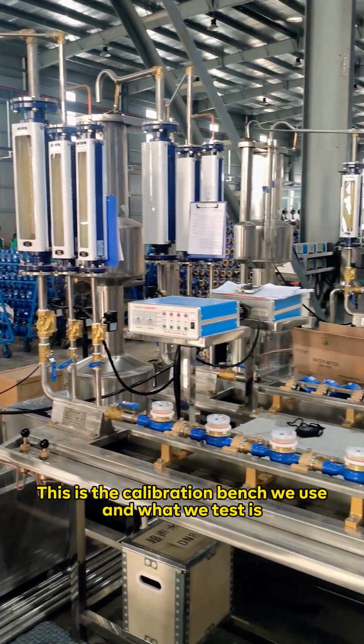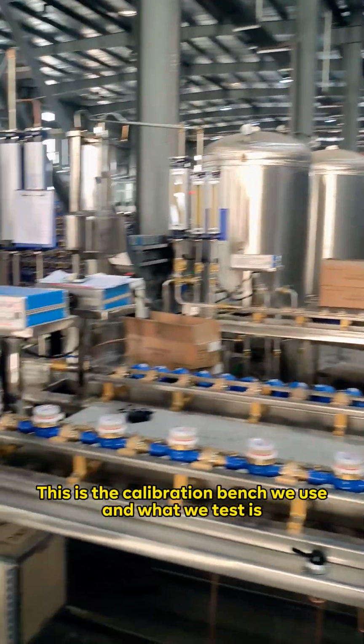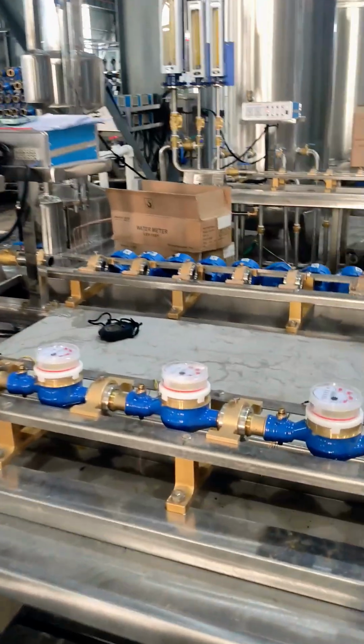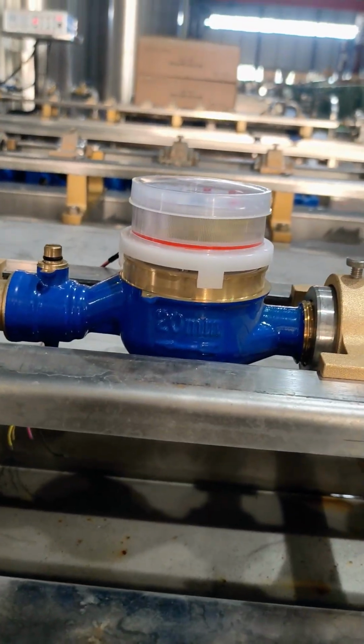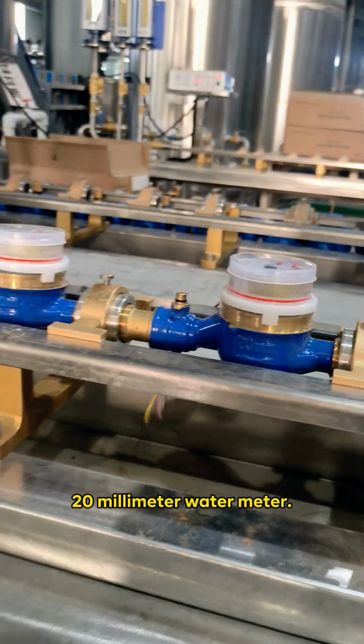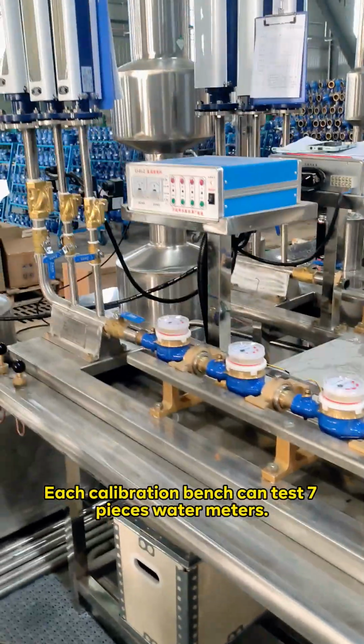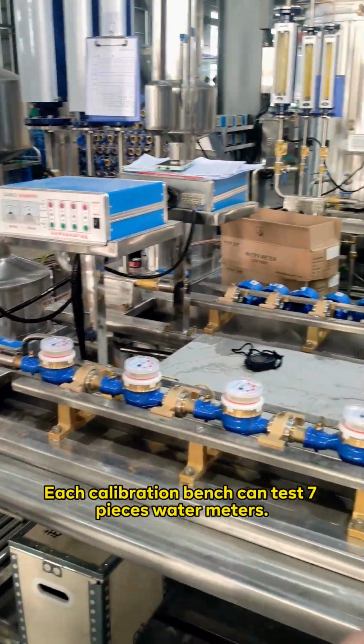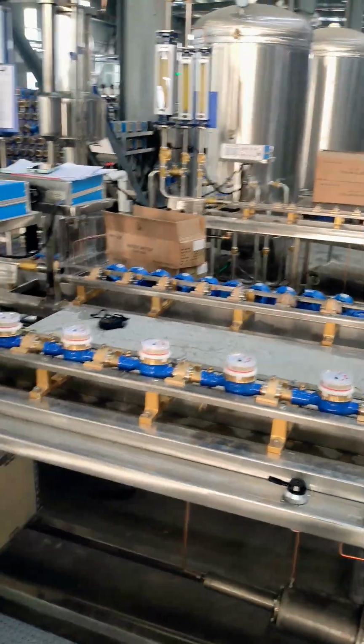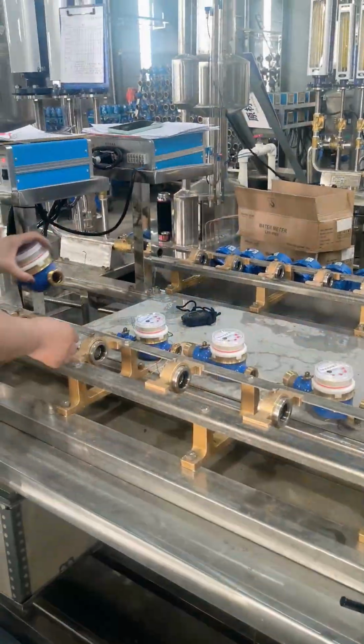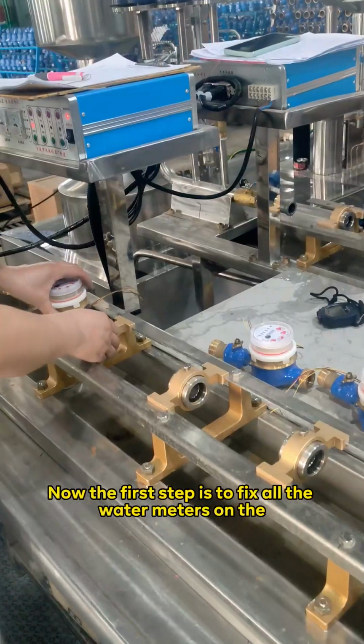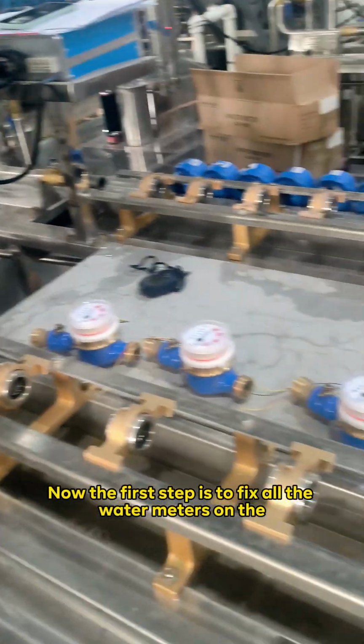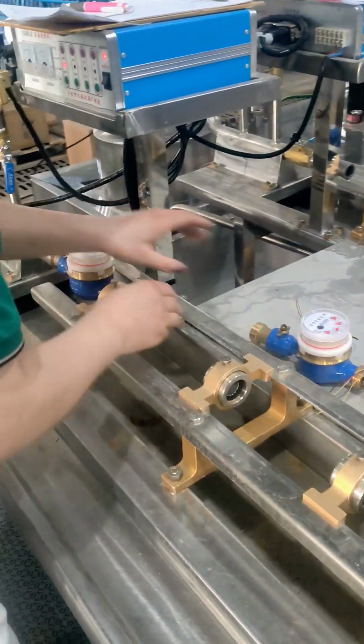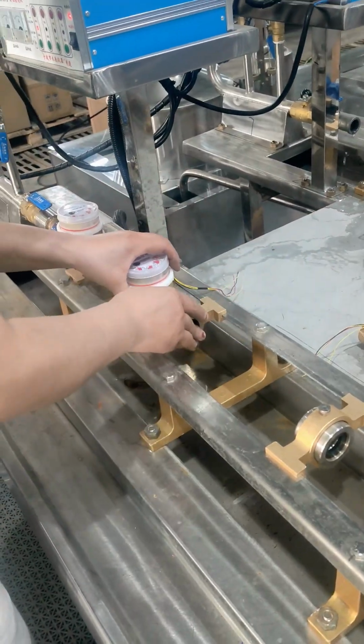This is the calibration bench we use, and we test the 20 millimeter water meters. Each calibration bench can test 7 water meters. Now the first step is to fix all the water meters on the calibration bench.